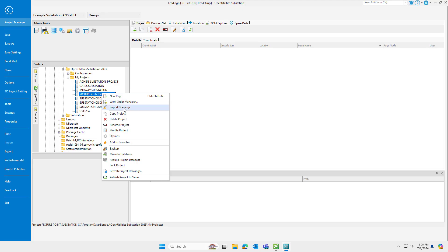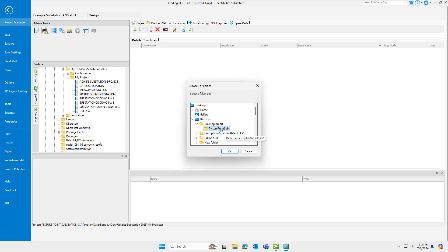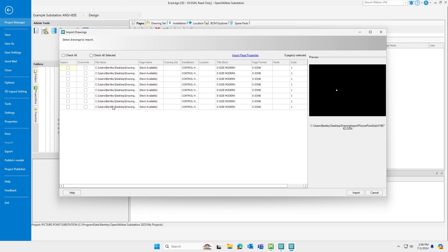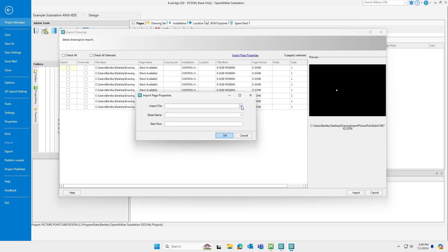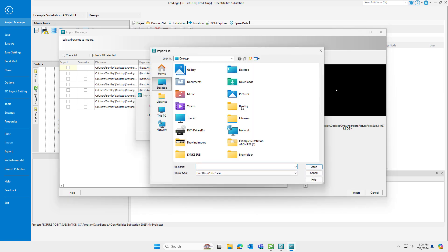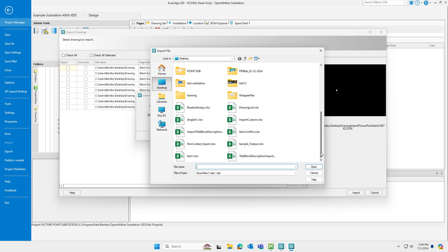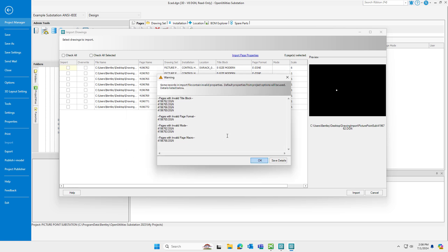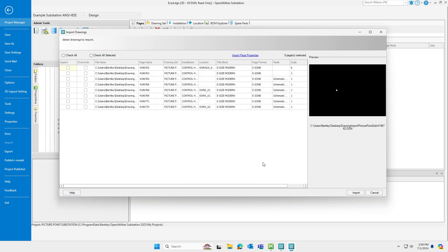I'm going to go ahead and access the import drawings tool. I'll select the folder containing the DGNs that I wish to import. And here you can see I have a handful of different DGNs available. Import page properties. This is the new tool found right here. When we click on that, I can select the Excel file that I want to pull data from. I can specify the sheet name and also a starting row. During the import process, should there be any issues with your data not aligning with your Open Utilities substation configuration, you'll see that in the window here. For example, invalid title block specified, invalid page format, invalid page mode, invalid page macro. You have the option, if this list were to be very large, you have the option to save details to a log file, a text file, and you could review that. In this case, I'll just go ahead and hit OK.